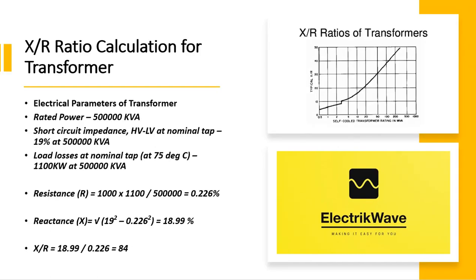Now let's calculate X by R ratio of transformer for the given electrical parameters. Rated power is 500 MVA, short circuit impedance between HV and LV winding at nominal tap is 19% at 500 MVA. Load losses at nominal tap and at 75 degrees Celsius is 1100 kW at 500 MVA. X by R ratio depends on load losses, rated power, and impedance value, and the X by R ratio is 84 for these parameters. No load losses has no effect on X by R ratio.